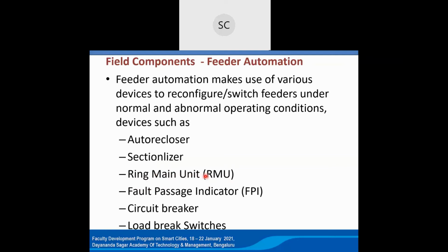The advantages of the ring main unit: it is also not a new concept. Even 20 years back, we installed enough ring main units in our distribution systems. But if anything happens, manually the lineman has to go and change the directions. A ring main unit helps here. For example, it may be getting inputs from 2 feeders, with one normally open switch, feeding 2 independent paths. I will show diagrammatically how it works.